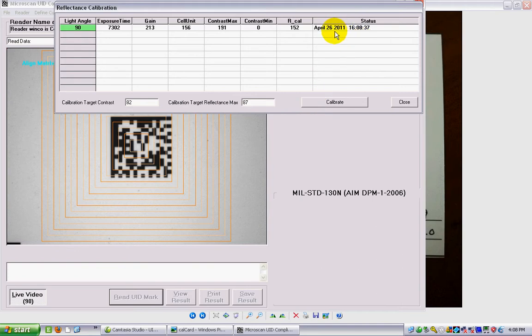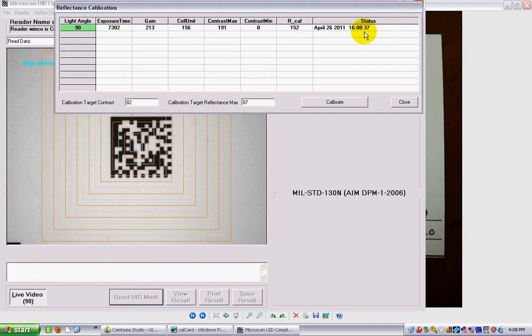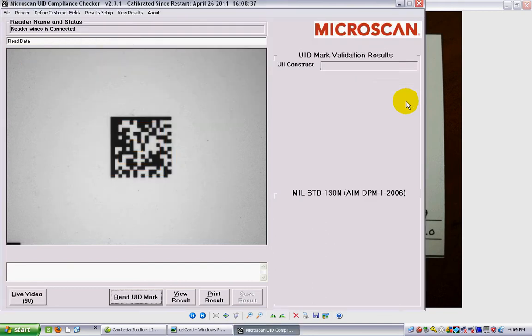You can see it's given me a new date and time of when the calibration was done. I don't think it's really that necessary to calibrate this too regularly. We usually calibrate our reader once a week or something like that. I know other people leave it on longer periods, but that should be good to go.